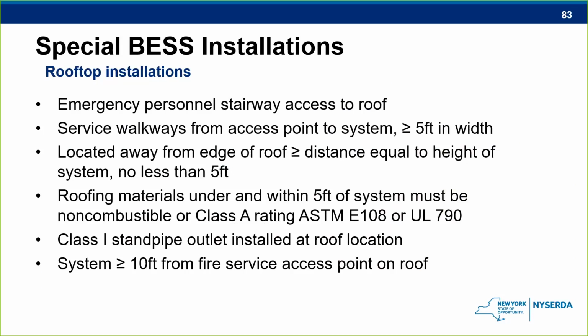Rooftop installations, promised to bring this back up again earlier too. They should have a roof access point from inside the building for first responders to use. The roof should have a standpipe that the fire service can use to put water on the fire if necessary. And the system cannot be within 10 feet of the roof access. You want them to be able to get up there safely without running right into it. And it also needs to be at least 5 feet away from the roof edge. All of these distances are used to safeguard the fire department operations response.